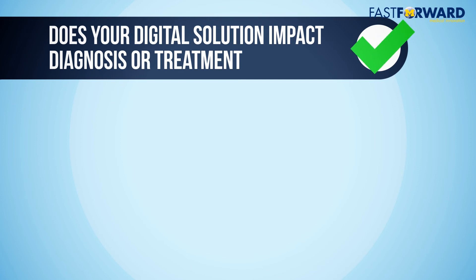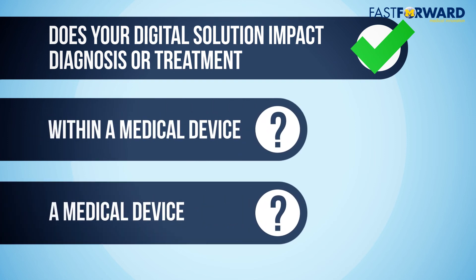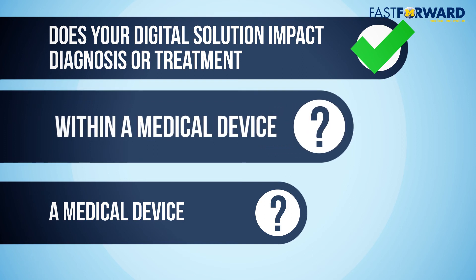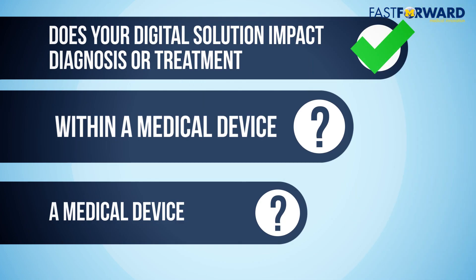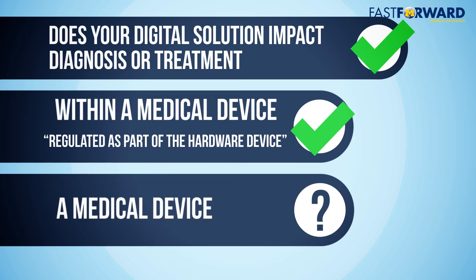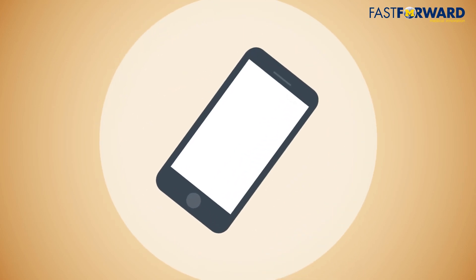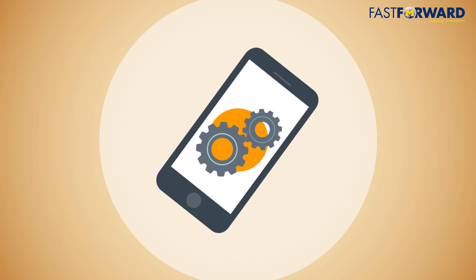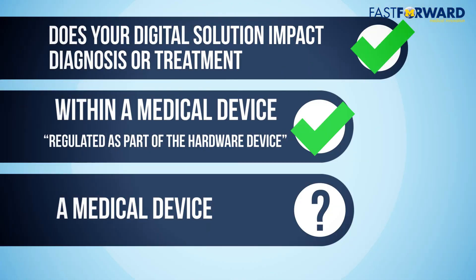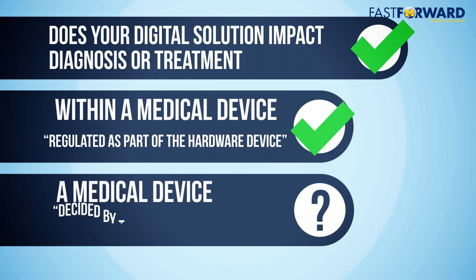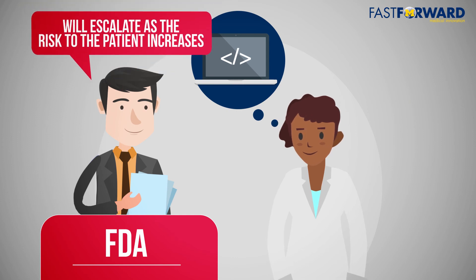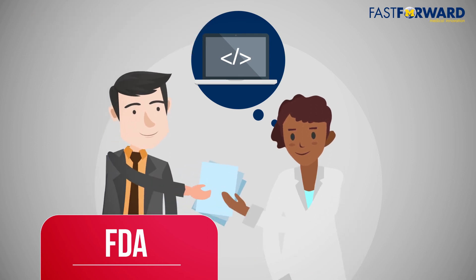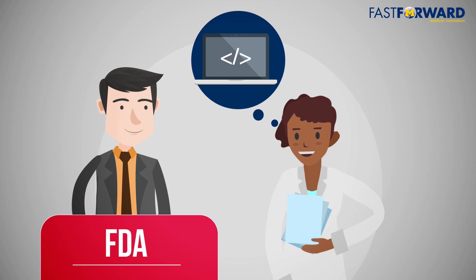If your technology most likely requires FDA regulation, how is it regulated? Is your digital solution within a medical device? Does it drive hardware that accomplishes the intended purpose? For example, software driving an IV infusion pump on its own does not have any effect unless it is coupled with an IV pump. If the answer is yes, the software will likely be regulated as part of the hardware device. Alternatively, is the software itself classified as a medical device? For example, a mobile app that can take a picture of a mole and make a diagnosis or recommendation would be classified as a medical device. If your digital health technology is regulated by the FDA as a medical device, the regulatory pathway will be decided by the intended use and indications for use of the technology. The amount of FDA regulatory oversight will escalate as the risk to the patient increases. The FDA has released several guidance documents to help you understand and identify exactly where you fall within the spectrum of regulation.